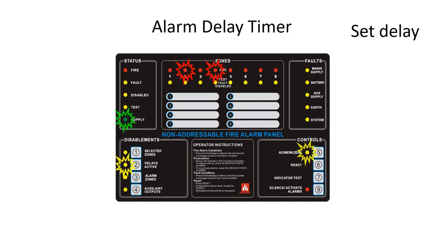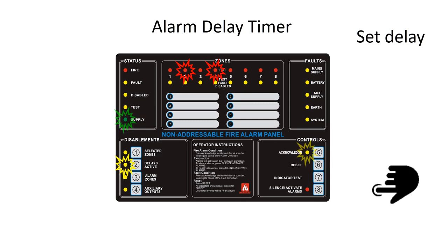The Delays Active LED will be on and the Acknowledge LED will continue to flash. If an alarm delay time has already been set, the time will be shown on the first 4 red zone LEDs. The companion yellow zone LEDs will be used to display the new delay time. In the example shown here, the delay time has already been configured for 6 minutes. We will change the delay to 3 minutes. Use the Silence Activate Alarms button to select a new delay time.